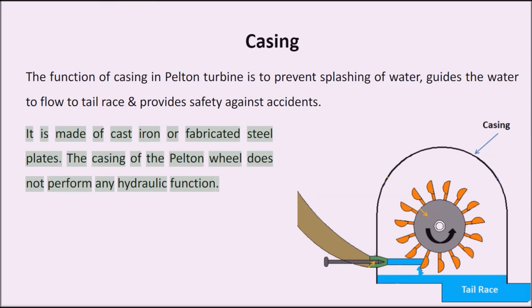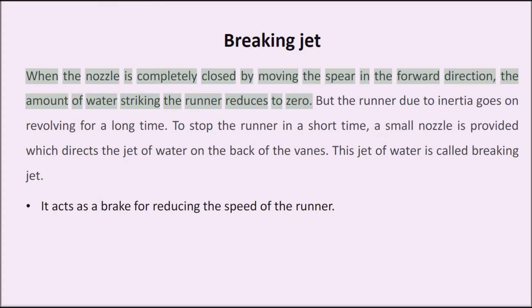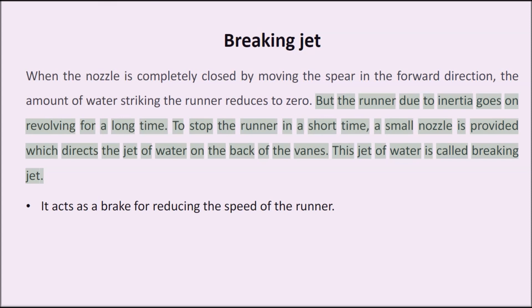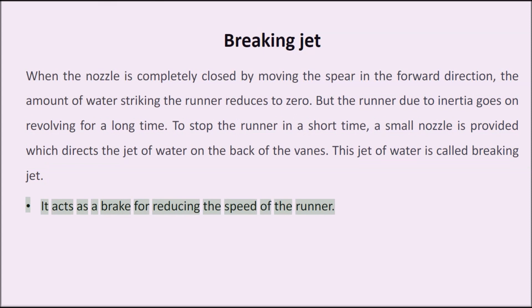Braking jet: When the nozzle is completely closed by moving the spear in the forward direction, the amount of water striking the runner reduces to zero, but the runner due to inertia goes on revolving for a long time. To stop the runner in a short time, a small nozzle is provided which directs a jet of water on the back of the vanes. This jet of water is called the braking jet and it acts as a brake for reducing the speed of the runner.